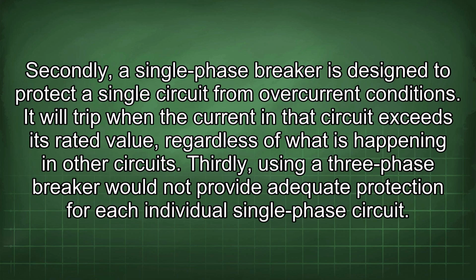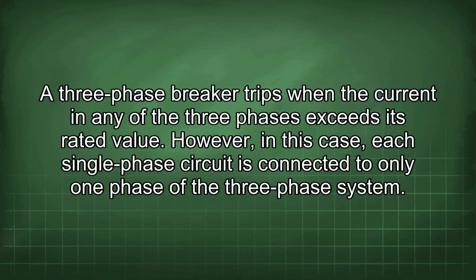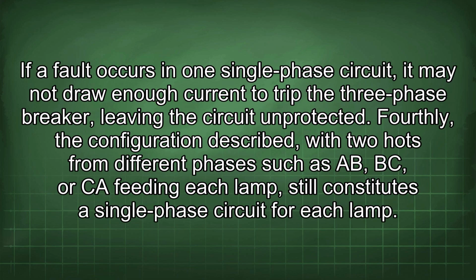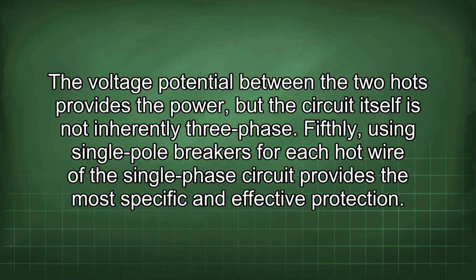circuits. Thirdly, using a 3-phase breaker would not provide adequate protection for each individual single-phase circuit. A 3-phase breaker trips when the current in any of the 3 phases exceeds its rated value. However, in this case, each single-phase circuit is connected to only one phase of the 3-phase system. If a fault occurs in one single-phase circuit, it may not draw enough current to trip the 3-phase breaker, leaving the circuit unprotected. Fourthly, the configuration described, with 2 hots from different phases such as AB, BC, or CA feeding each lamp, still constitutes a single-phase circuit for each lamp. The voltage potential between the two hots provides the power, but the circuit itself is not inherently three-phase.